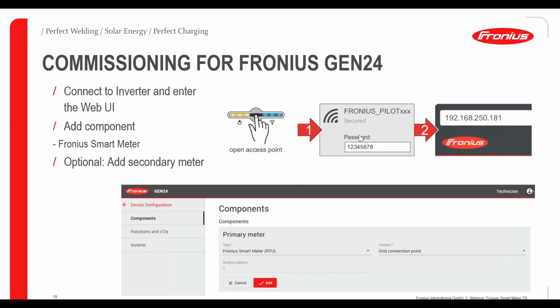So once in the web interface of the inverter, under device configuration and components, you can simply add a smart meter here. You find the Fronius smart meter, and the positioning of the smart meter here, in this case, is feeding point, and you just add it. Modbus address 1, you just add it. If you have a secondary smart meter, you do the same for the second smart meter. You save it and you proceed.